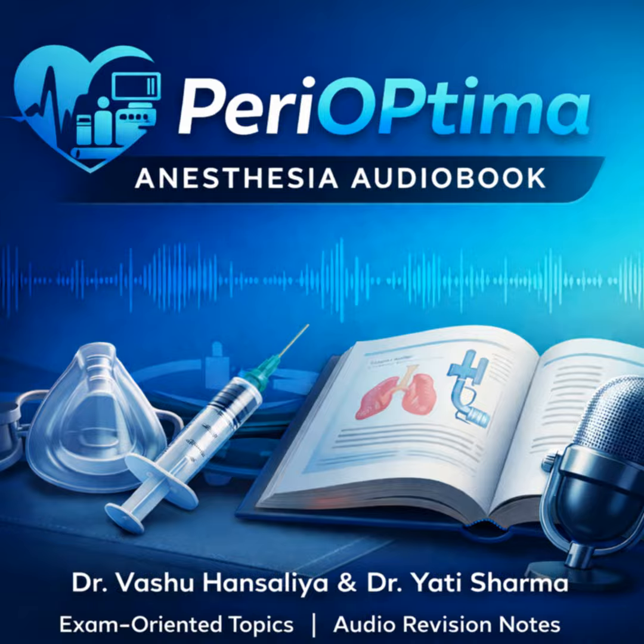They test the integrity of that inner tube. Number 1 is Pethick's test or the Venturi test. How does that work? The procedure is you occlude the patient end of the outer tube. You close the APL valve. Then you flush the inner tube with a high flow of oxygen, say 5 to 10 liters per minute.